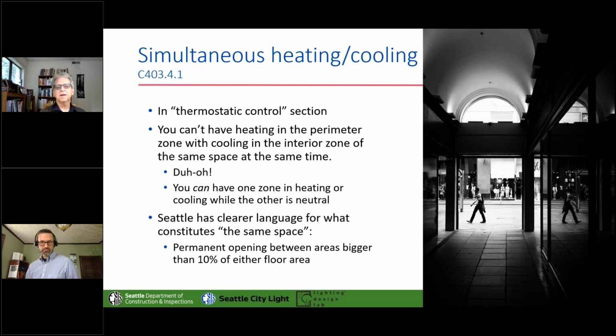We've made it clear that as opposed to conventional practice, you can't be heating out of the perimeter at the same time you're cooling in the interior of the same space. You'd think that would be so obvious, but mechanical engineers have always believed in a magical invisible barrier 15 feet in from the window wall that separated those two zones and kept them apart. What we've said now is, no, it's the same space, and we've defined how you determine, in case it's an odd-shaped space, what all qualifies as the same space.